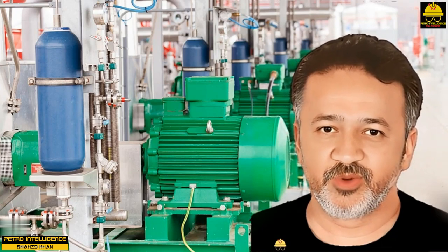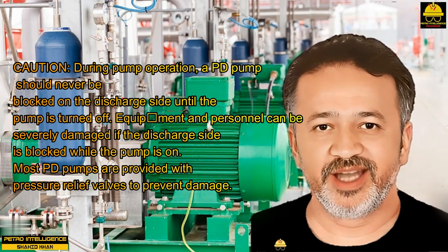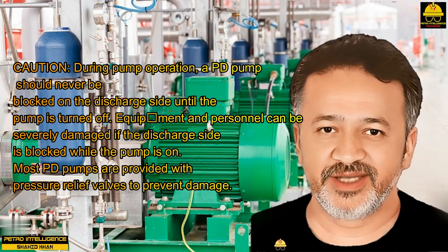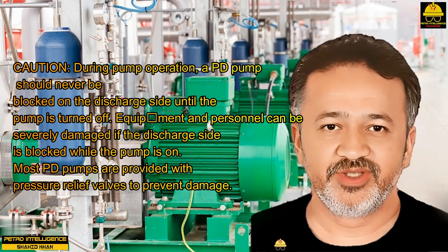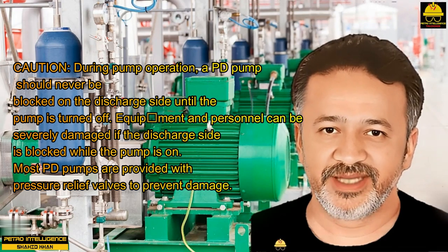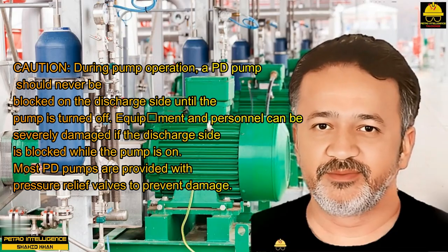You must be cautious during pump operation. A PD pump should never be blocked on the discharge side until the pump is turned off. Equipment and personnel can be severely damaged if the discharge side is blocked while the pump is on. Most PD pumps are provided with pressure relief valves to prevent damage.